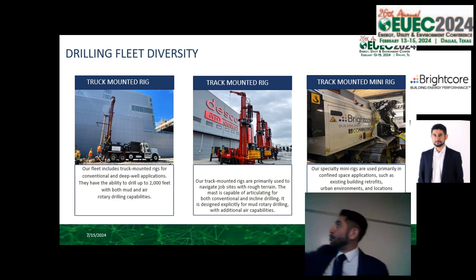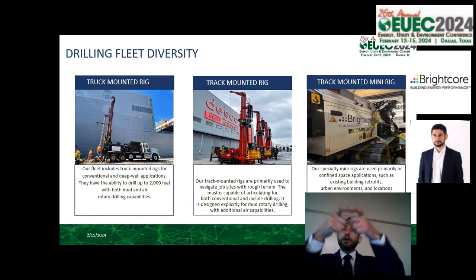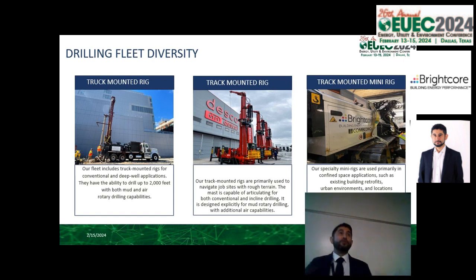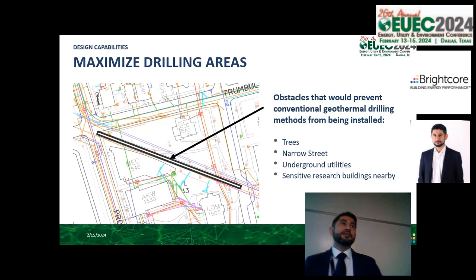What's nice is the track-mounted rigs in the middle and on the right get through a lot of nooks and crannies, but can also go angled—it doesn't have to be vertical. That means you can have a small surface footprint while maximizing thermal load and residence time for the loop to drop off or pick up heat depending on ambient temperature. A good example is when you have a lot of infrastructure to get around and don't know where to go. Classically, this would have been a line of 20-foot off-center vertical boreholes, limiting your tonnage, so it may not pencil.